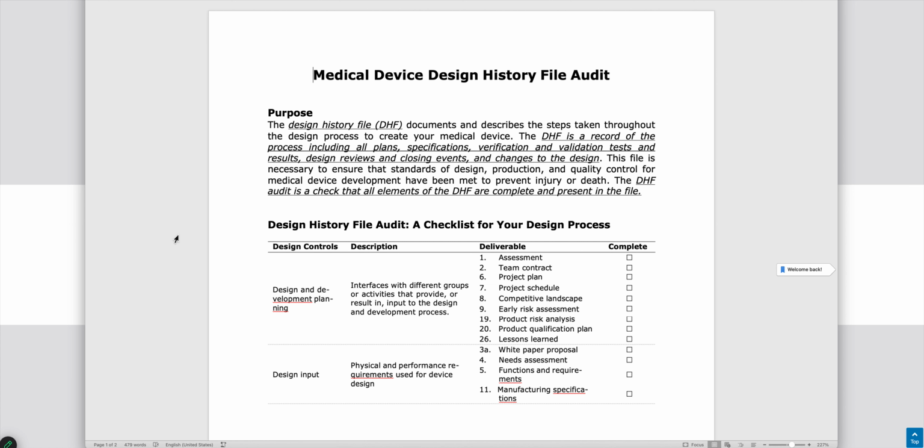So we understand that when an auditor goes to any facility where they are making medical devices, they are looking into the design review, the design plan, the design input, the design output, and of course several other documents that they will have to make sure exist and are documented. We call those deliverables, which we are going to see in the next table.